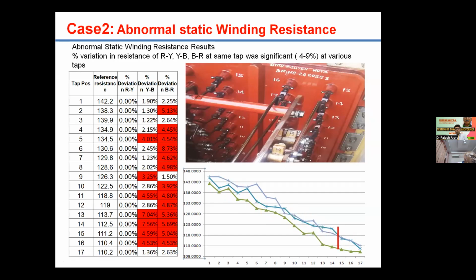You can see it from the graph also, the pattern is not uniform. Sometimes we are seeing a rise in resistance also. So it was decided to inspect this transformer's OLTC, because the kind of variation on all the taps indicates there must be some problem with the moving contacts of the transformer. Only then can it happen that all the taps are showing some kind of variation.